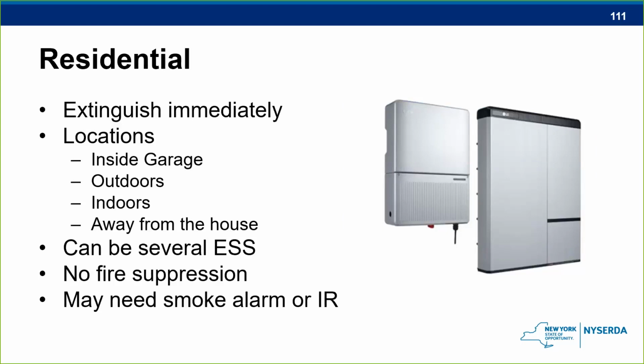Residential. If you are at a residential fire and it has an energy storage system, that communication should be put on the fire ground immediately, right? We also would start to extinguish this thing immediately. We can throw a hose line right onto the actual cabinet itself that may be adjacent to the wall. Some of them are going to be attached right to the wall. We want to get this thing out as quick as possible. As I said before, stay a distance away, up to 10 feet, making sure you have that 10 degrees on a fog nozzle, and try to knock down those flames so it doesn't propagate into the structure itself.